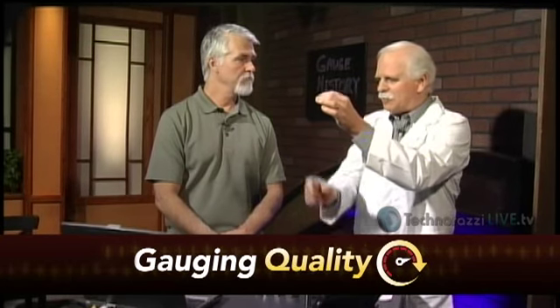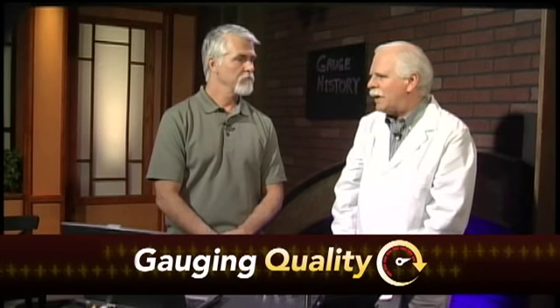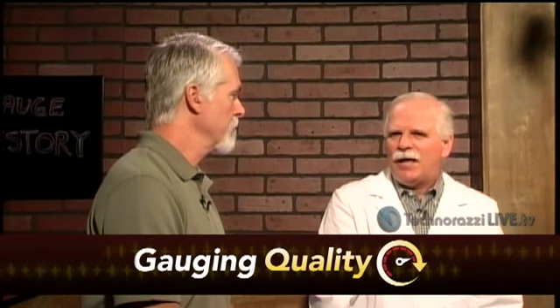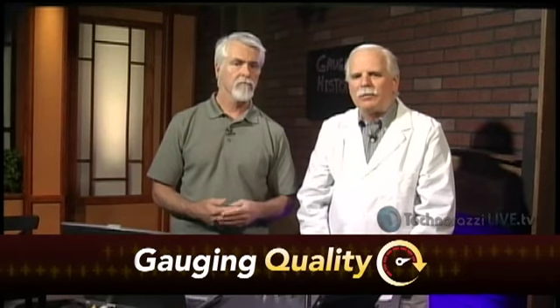Another example of the actual value of a gauge or the actual measurement might be a thermometer. Let's take a liquid and glass thermometer. It's a tall piece of glass with a very thin capillary. As that capillary ages, it widens a little bit. It's very thin, so the mercury, the fluid, will drop dramatically. You would know if it's always been very stable. It's always stayed the same. All of a sudden, it's dropped a degree or two, something has changed. It's more of an indication of what's changed. It still measures what it measures that day. But this will help you in your decision process on what's gone wrong. So that would be the actual measurement over time.